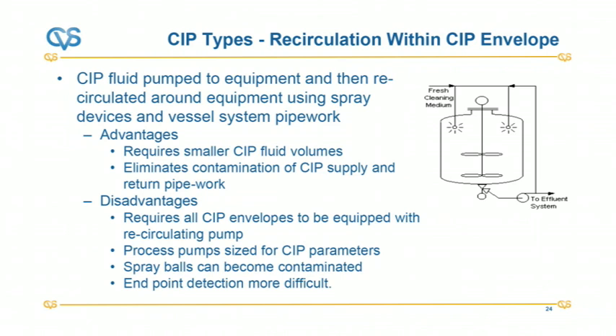The third type is recirculation within the CIP envelope. So basically, we put our CIP medium through our spray balls, and we then keep recirculating it. And then there may be a few cycles where you put some more in and recirculate and run to effluent. So you're using the process pump to actually clean the system through the spray balls. In some cases, this could be hard coupled or flexible coupled, depending, and then transferred so that you could put water in as well. So here, the CIP fluid is pumped to the equipment and then recirculated around the equipment with the spray devices.